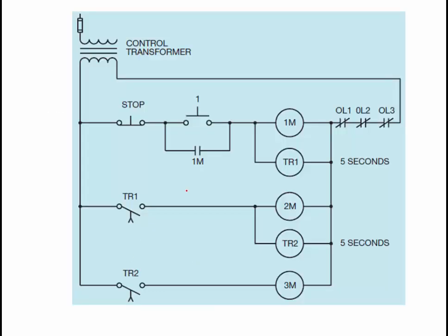Now we could also use timing relays. It's a little more pretty and this is probably a little more common. Why would you want to have timing relays? Well one reason is motors have inrush. So if these three motors 1, 2, and 3, if we start them all at the same time we might have just tremendous amount of inrush current and the system can't handle it. But if we start them one at a time we let things settle out. So these have a 5 second delay between them.